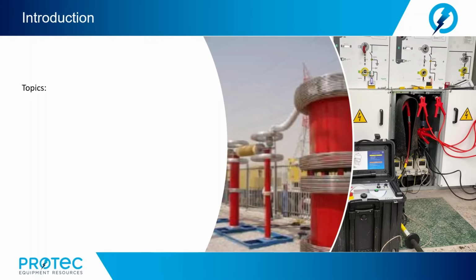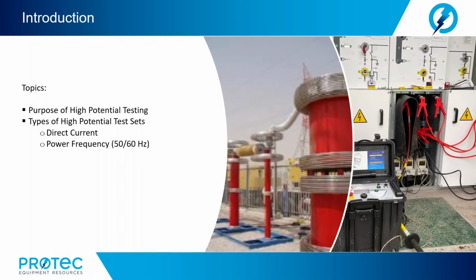Now, our main topics for this webinar are going to be the purpose of high potential testing, types of high potential test sets, test equipment. We're going to talk about DC or direct current test sets, power frequency operating at the 50-60 hertz frequency level. We will talk about near power frequency or resonant test sets, which will operate anywhere between 20 hertz to 300 hertz depending upon the load that they are connected to. We'll also take a look at very low frequency or VLF test sets.